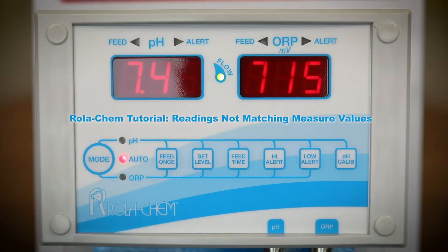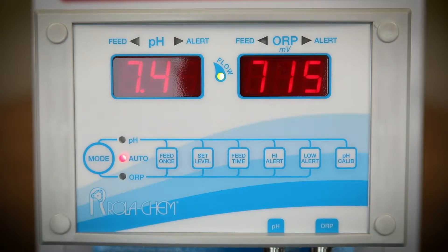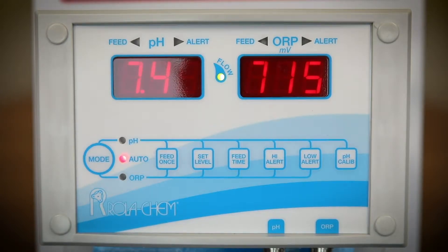In this segment, I want to further troubleshoot the 554-series Rola-Chem controller. Should the controller displays read settings that do not correlate with the DPD-tested chemistry — for example, if the controller is reading 0 for ORP and 6.0 for pH — this indicates that the probes are attached to the incorrect connector.